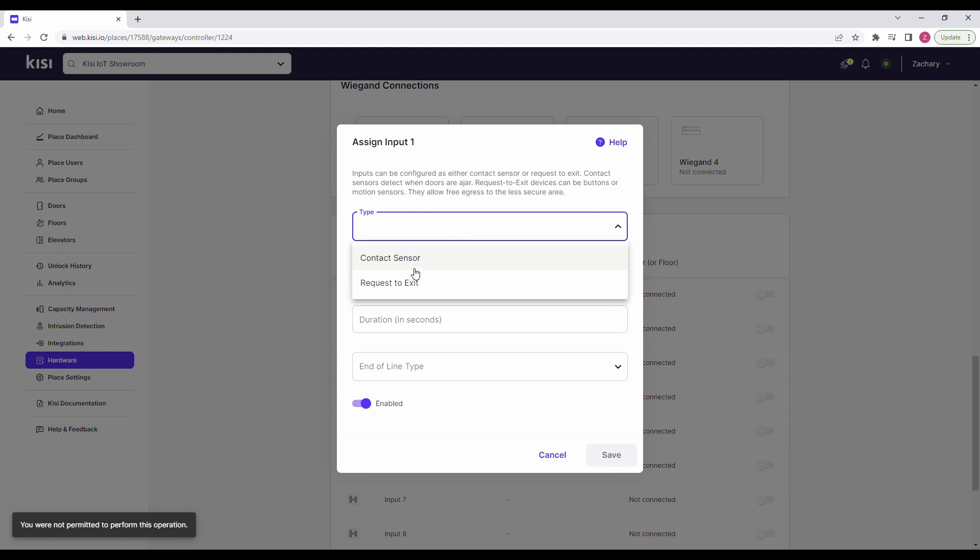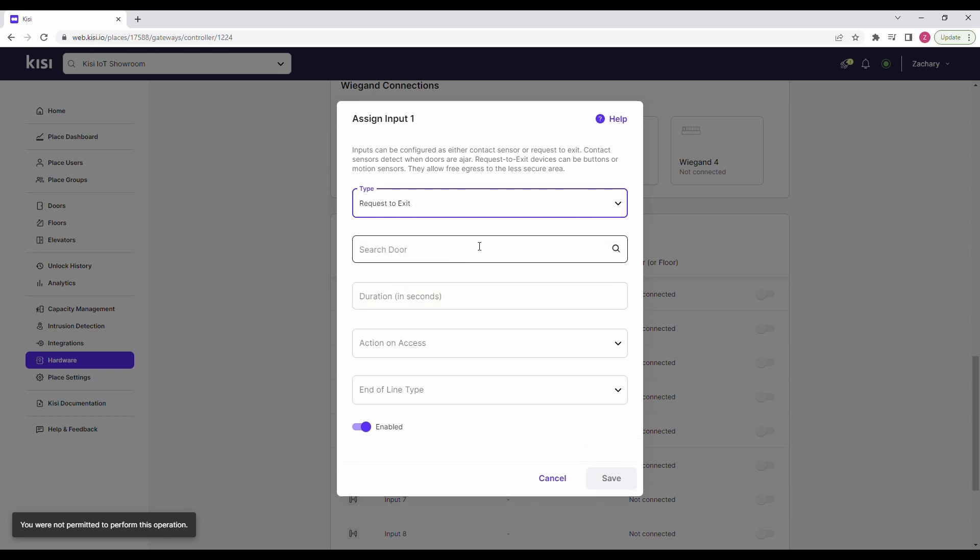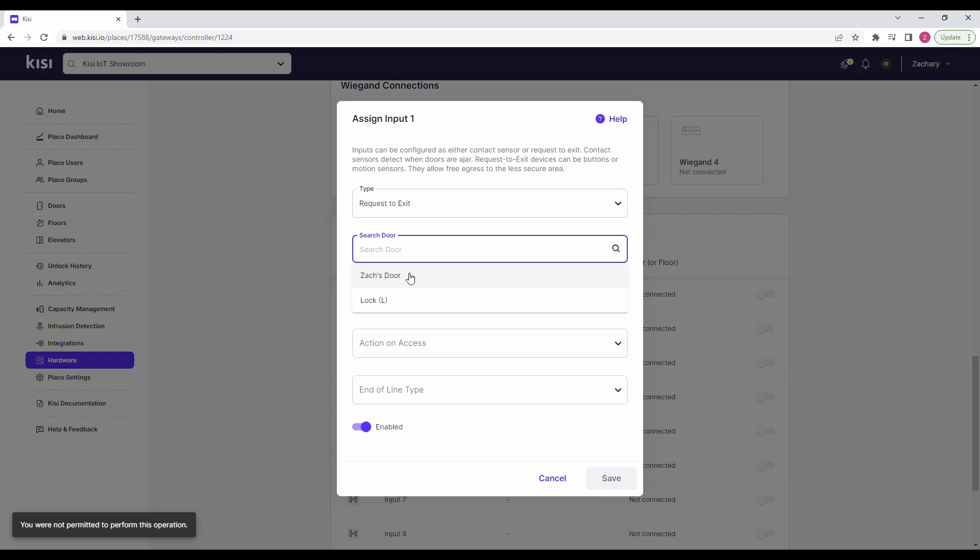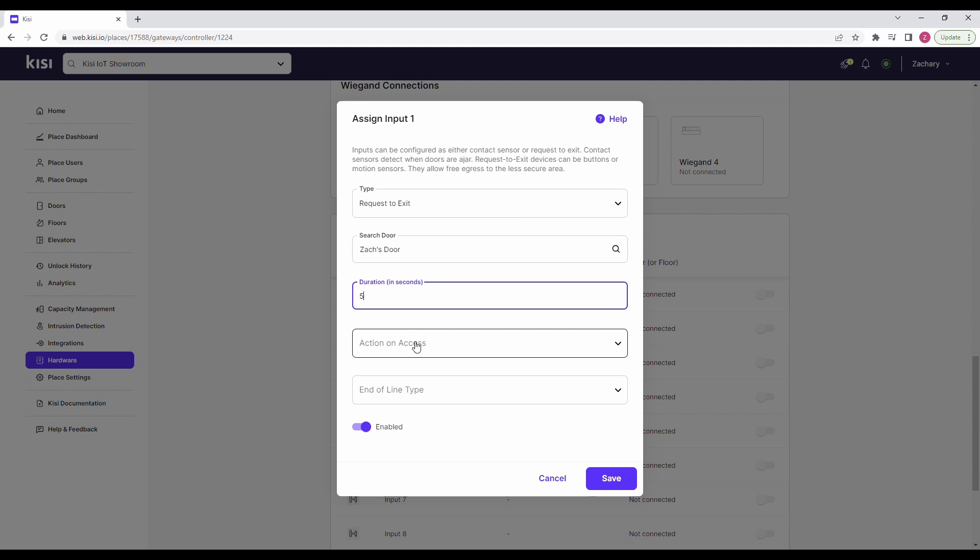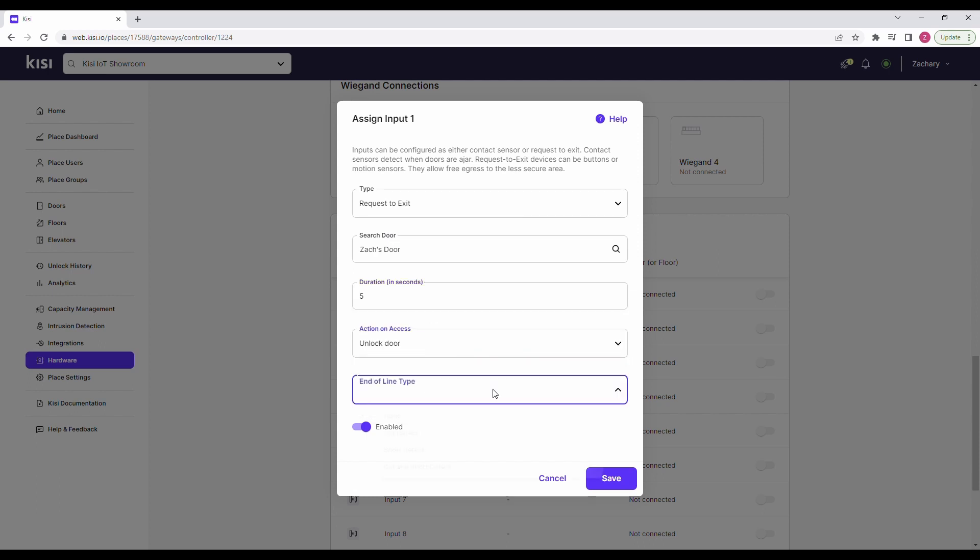Under Type, select Request to Exit. Under Door, select the door the request to exit device is wired to. Under Duration, define how long the relay should be triggered. Under Action on Access, select Unlock Door. Under End of Line Type section, specify the desired end of line status that you want Kisi to detect. Enable the toggle and click on Save.